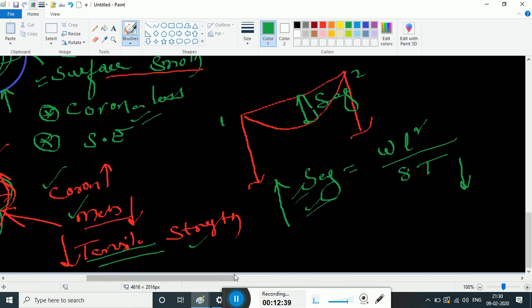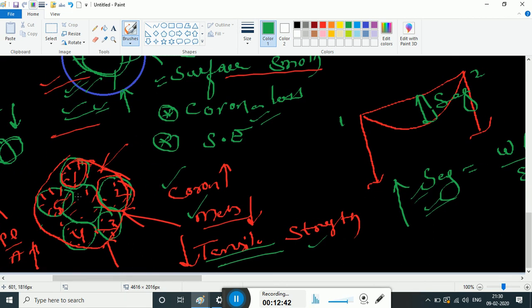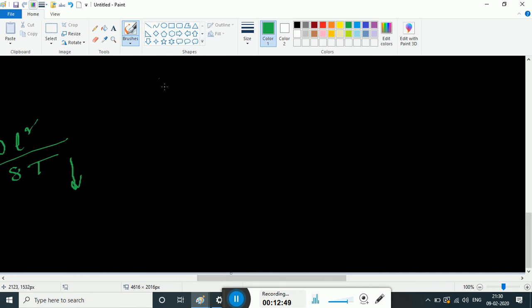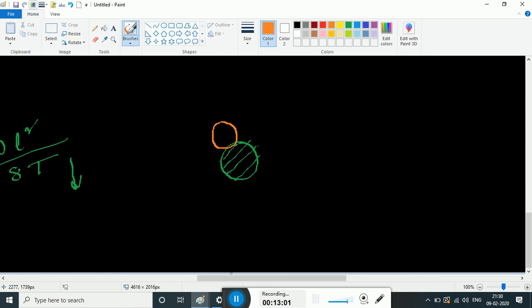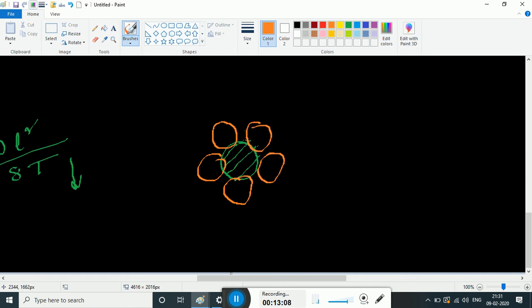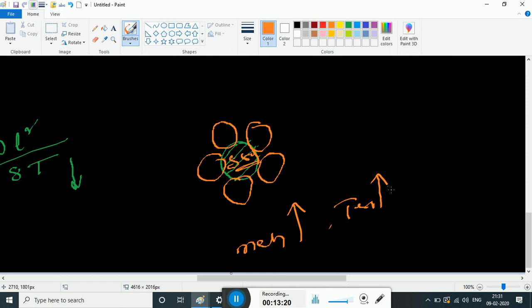To overcome these problems, we place steel in the middle of the conductor — that is the ACSR conductor. With steel in the middle, mechanical strength increases and tensile strength also increases, so SAG decreases.